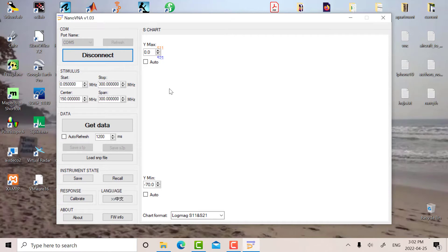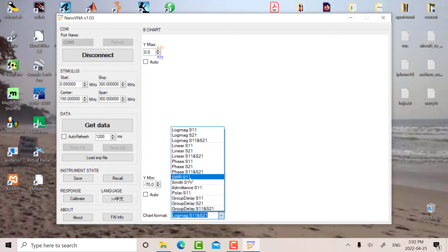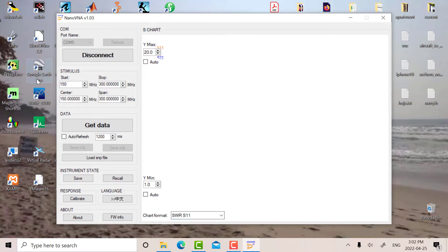Okay, so now we're connected and what we're going to do is calibrate first. I'm going to set this thing up for SWR and S11 port 1, and we're going to go from 150 to 180 megahertz.